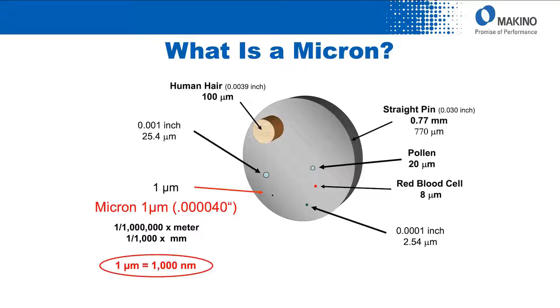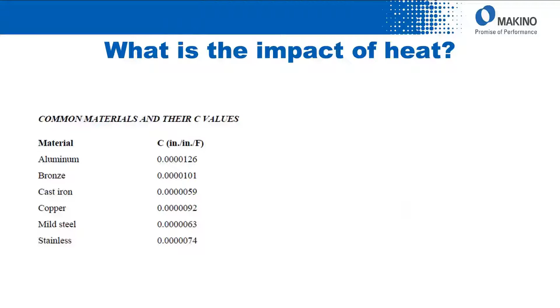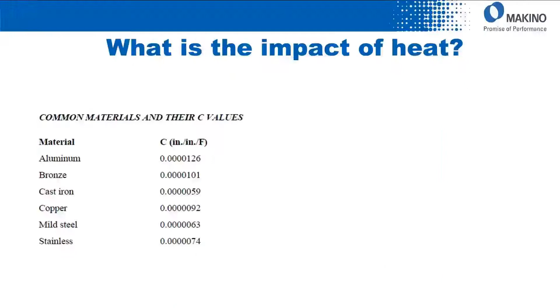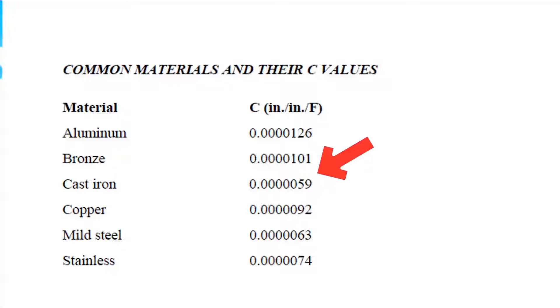What's the impact of heat? Every material - you'll see aluminum, bronze, cast iron - every material has what's called a C factor, the coefficient of linear expansion, in inches per inch per degree Fahrenheit. Aluminum is 12.6; steel and cast iron are 5.9. So aluminum grows a lot more than either cast iron or steel.